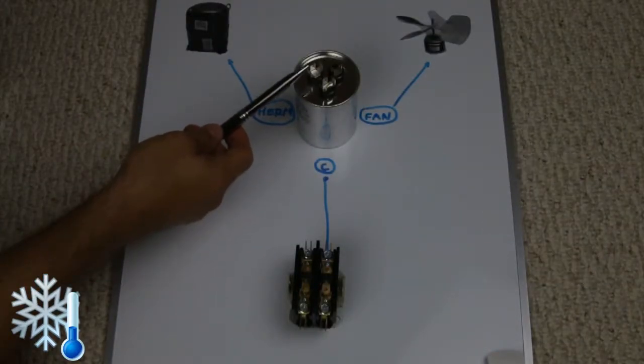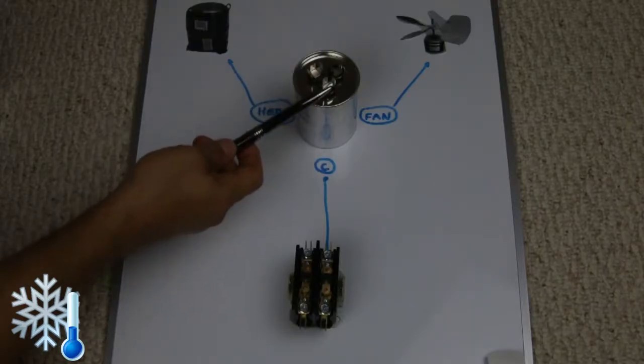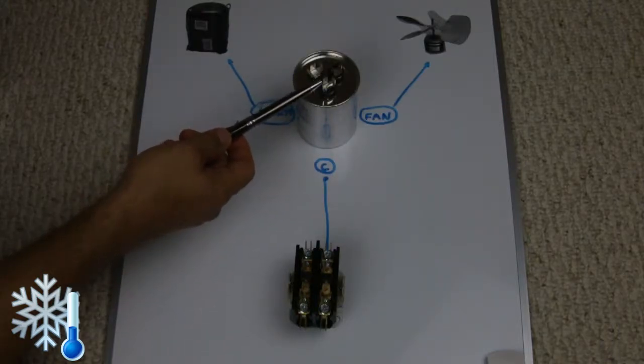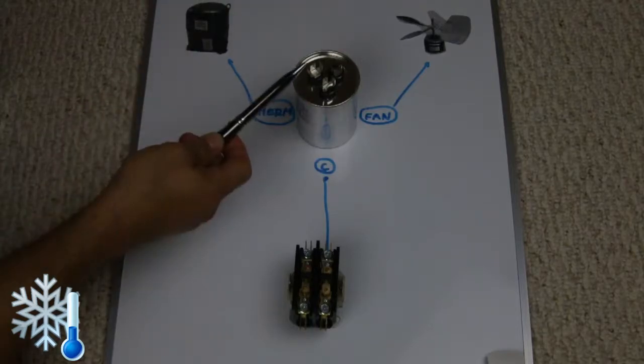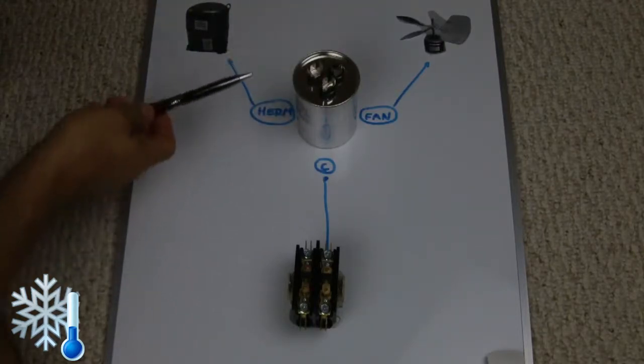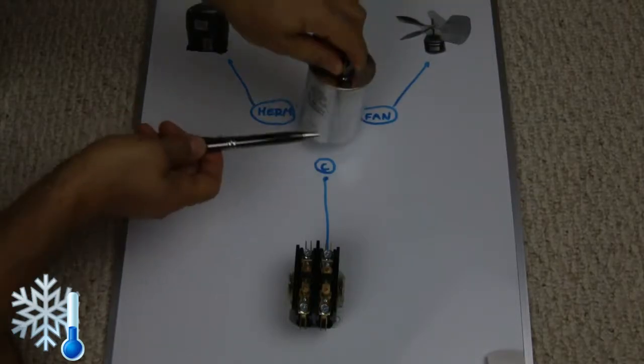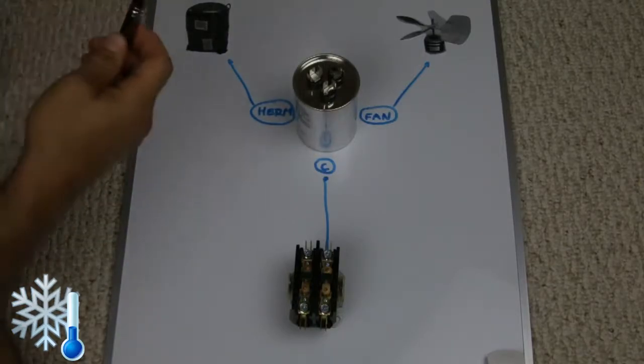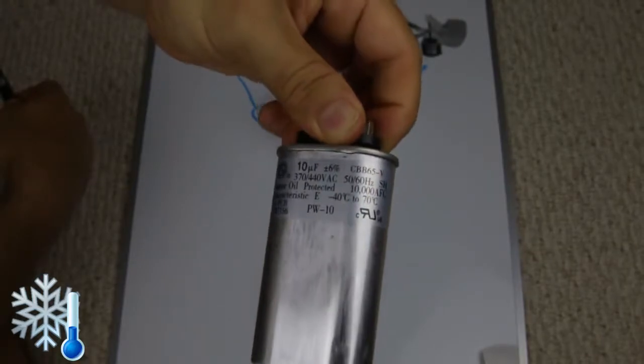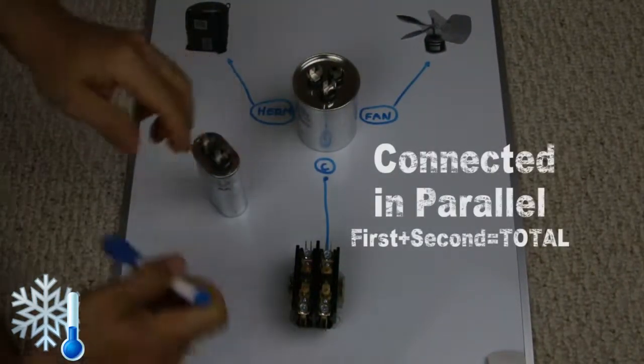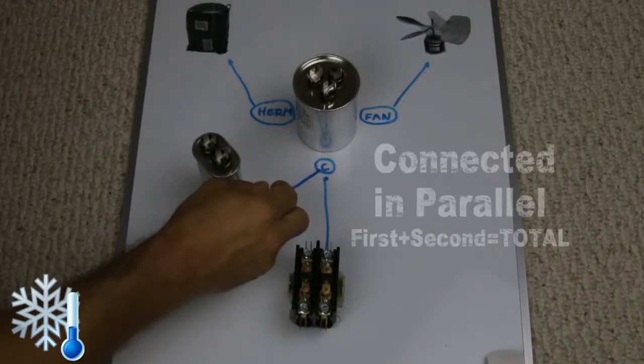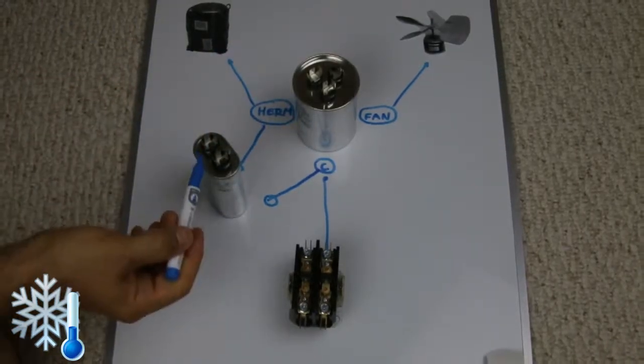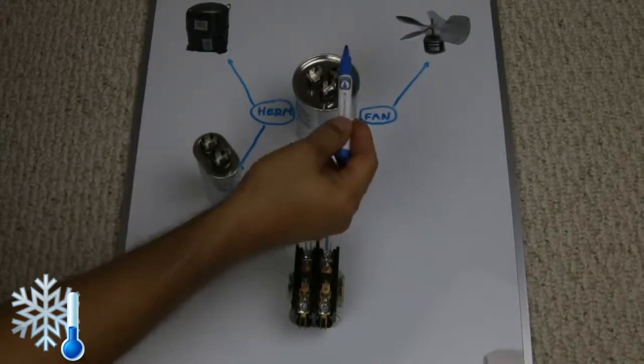What's the reason for multiple tips on every terminal? For example, the four for the common and three for the herm and two for the fan. That is if you want to add some additional capacitance. In our example we have a 45 plus 5. If you want to do a 55 plus 5, we can add an additional 10 microfarad to the system just by adding them to one leg going to the common and the second one going to the herm.